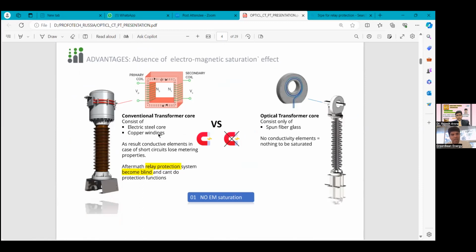Another advantage is the absence of electromagnetic saturation effect. If you see, the conventional transformer core consists of electric steel core and copper winding. As a result, the conductive element loses its metering properties in case of short circuit.